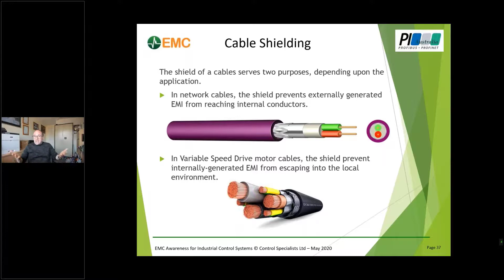Now, this is something we just have to accept. Certainly for some of you, I know you work for companies in process industries and in particular hazardous areas. Clearly I can't tell you not to follow the guidelines for hazardous areas - that clearly takes precedence. What I want to tell you is, if you're in a situation of having to follow safety guidelines, you follow them. But be aware that if that's the case, your shield will not protect you against everything, and that may be a problem - you may need to take other actions to mitigate against it. So just be clear: safety, hazardous area, etc., that takes priority, but that may conflict with this.